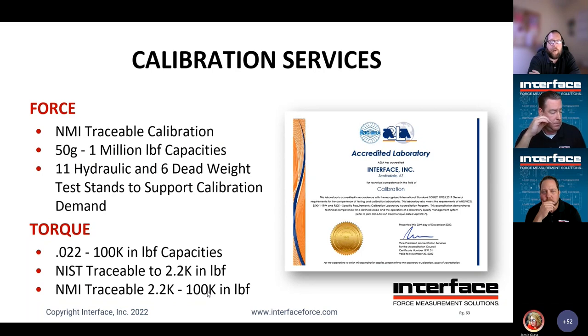For the torque, we can do all the way down to 0.022 up to 100,000 inch pound force capacities. We do also work with some outside partners for the higher capacities, which I believe we can do up to 200,000 on those as well. The calibrations are NIST traceable up to 2.2 thousand and NMI traceable up to 100,000. Next slide, please.